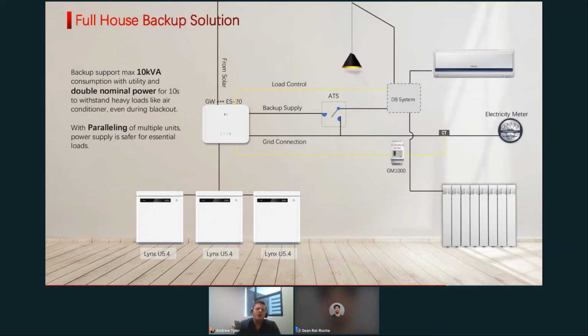Then we also have the option of using the load control feature to be able to switch an ATS. For those markets that typically don't get load shedding conditions, and might not want their house's loads to be connected completely to the backup, you do have the option to switch the relay to move the load over from the grid to your backup supply. This is a really nice feature for those that don't want it connected to the inverter permanently. So when the grid does fail, the load control can switch a relay that switches the backup circuit, or the ATS to the backup circuit, should I say.